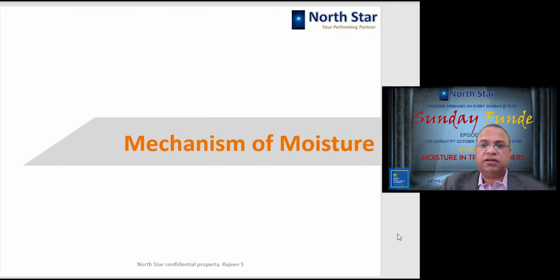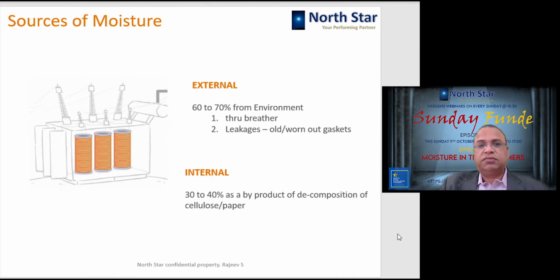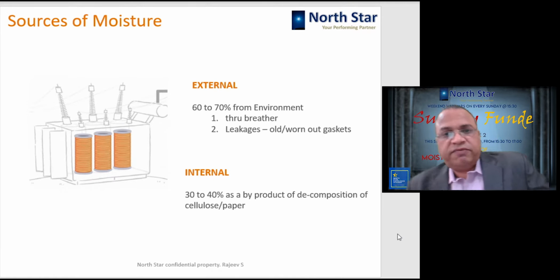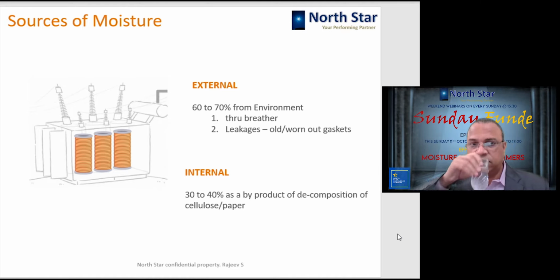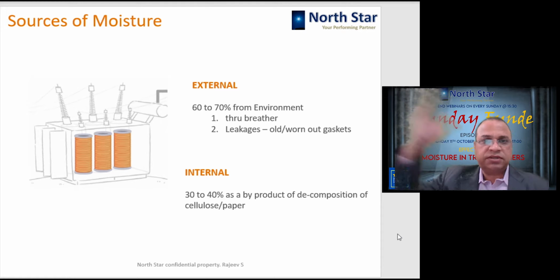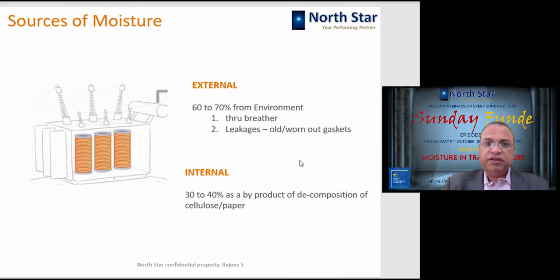Okay, so let us look at how moisture affects the transformer. There are two ways by which moisture can go inside the transformer. One is of course the environment, that is, external factors. We have a breather on the transformer, and you know that the breather has its own limitation because it absorbs the moisture and keeps it within itself. It won't throw the moisture away anywhere. So after some time it becomes saturated with moisture. As it gets saturated, it no longer absorbs moisture. So if nothing is done with such a breather, the moist air is allowed to go inside the transformer, and your transformer oil and insulation are subjected to the external moisture.